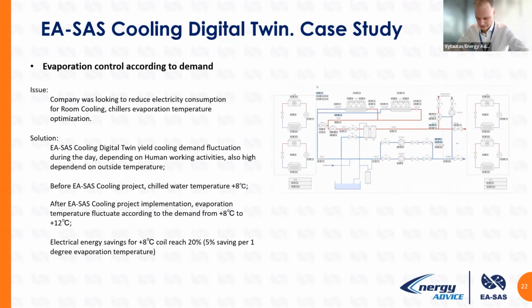Another type of system is the commercial side. It's not industrial, it's commercial. The company was also looking at how to reduce electricity consumption for the chilling process, and the compressor station is two chillers. One chiller consists of two compressors, and the other chiller consists of two compressors. It prepares cold water, maybe glycol, I don't remember now, and delivers it to the load. It was also +8 production. We established that it could work between +8 and +12, with savings of 20%.